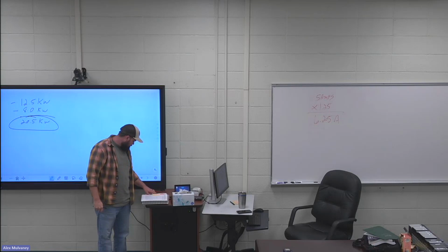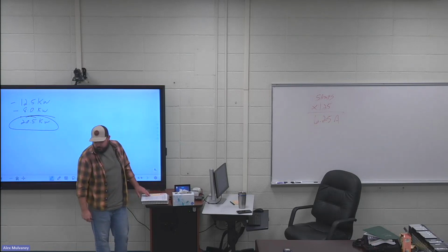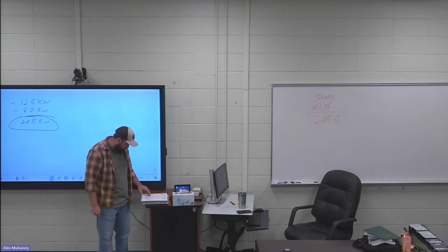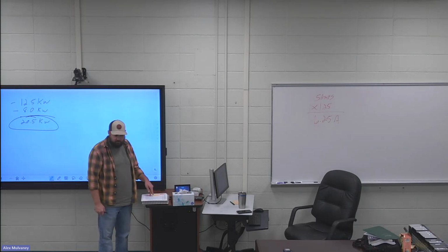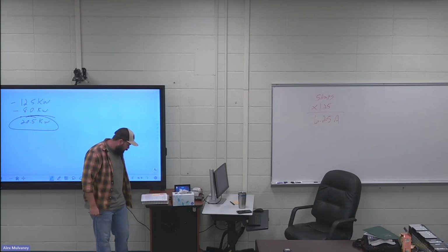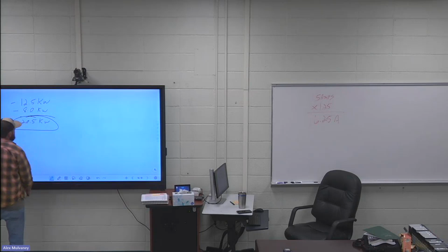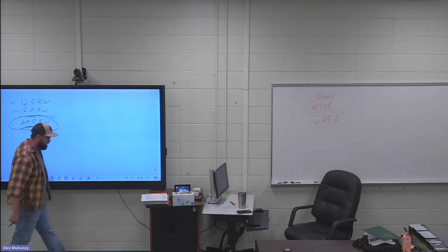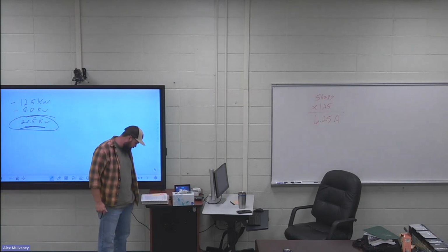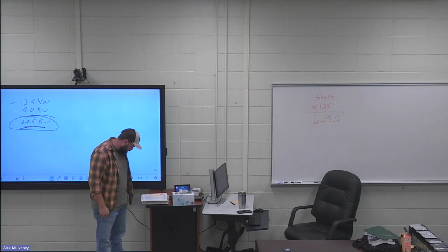Now we're going to note 1. All right, so we're on note 4. Now I'm going to read through note 1 on that same page. Again, this is a harder part of this. Note, over 12 kilowatts through 27 kilowatts. Are we there? Yeah, we are right in the mix of that. So we're over 12, but we're under 27 of all the same rating.